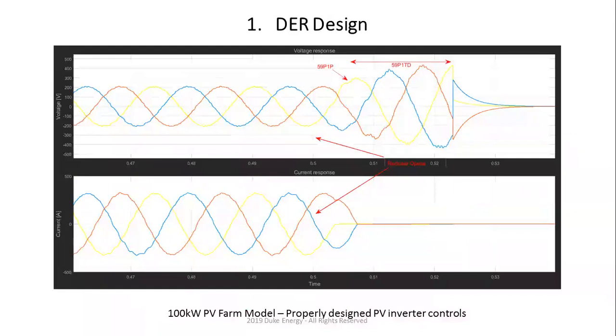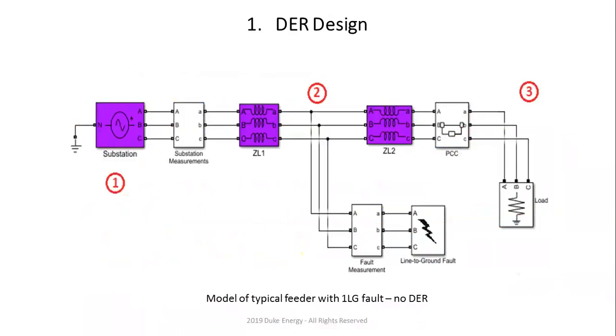And a lot of times when we simulate transitions, we actually turn off the battery just to show everybody what happens when we only have a PV system, right? Now, this is probably the most challenging part of the design, and a lot of PhD theses that I have reviewed have a particular configuration with the transformer, and that can actually cause all kinds of challenges on the feeder that we're going to talk about. So what I have done over here is taken just a typical feeder that has a substation, and I have introduced a line to ground fault somewhere in the middle.